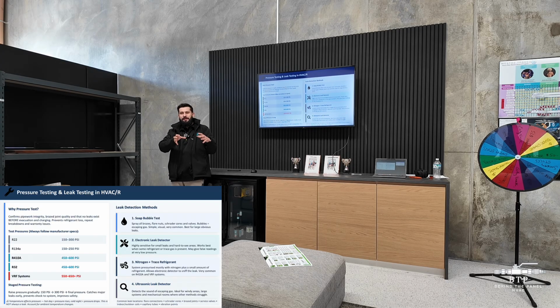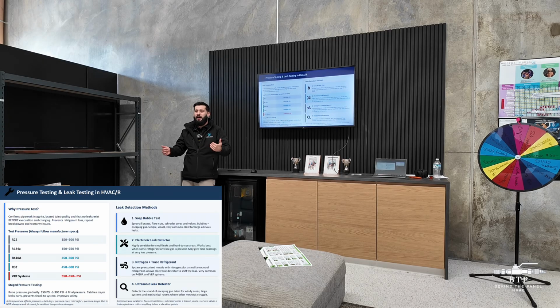Okay, so don't preset your regulator to 600 psi and only just open your nitrogen bottle. Don't do that. It's a big no. So always start at 0 and then slowly increase the pressure in your regulator. Build it up to about 200. This is my recommendation. This is what you can do. Build up to 200 psi and then start checking for big leaks.